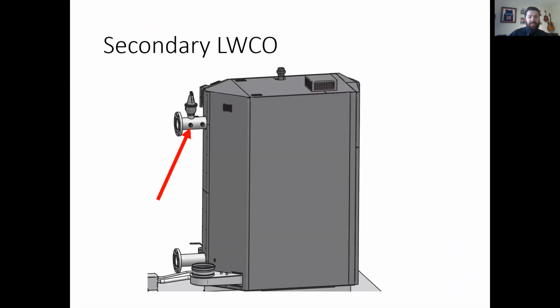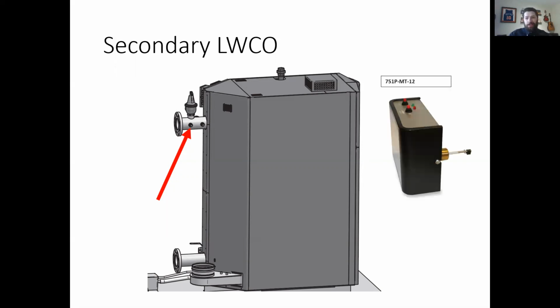You might see that your stack comes off the back there and goes up. Sometimes that's a little tight. You can put it anywhere in the line before your valve, okay? So right there where I pointed out is the best location, or anywhere nearby is good. This is usually what that little secondary cutoff is going to look like. We send it from McDonnell Miller, the Xylem brand low water cutoffs, and we're going to ship that with most of our boilers.